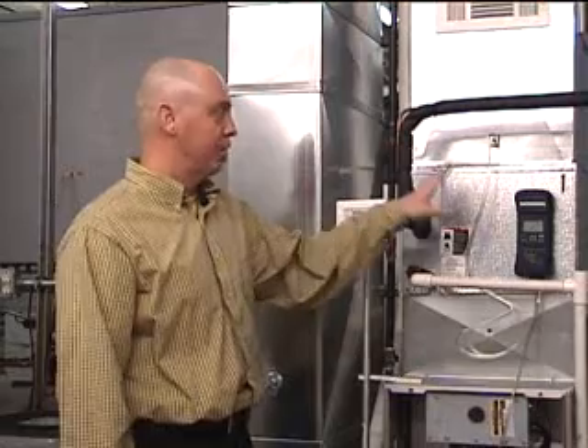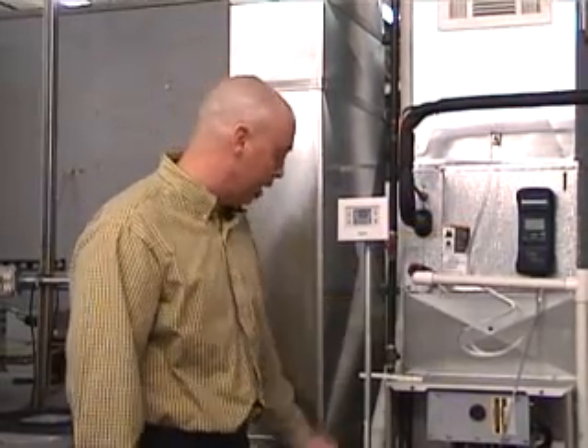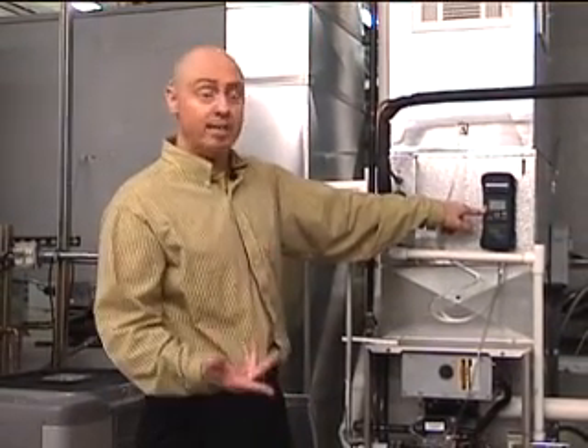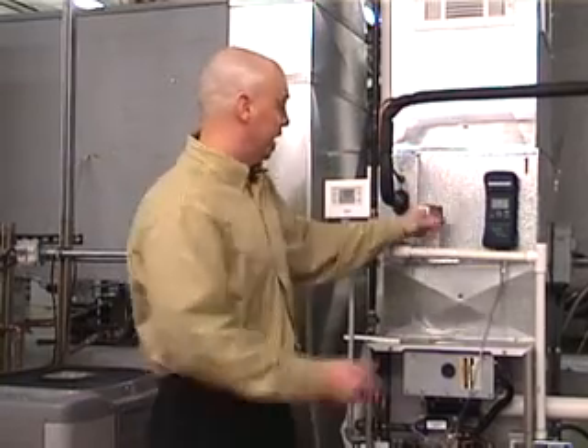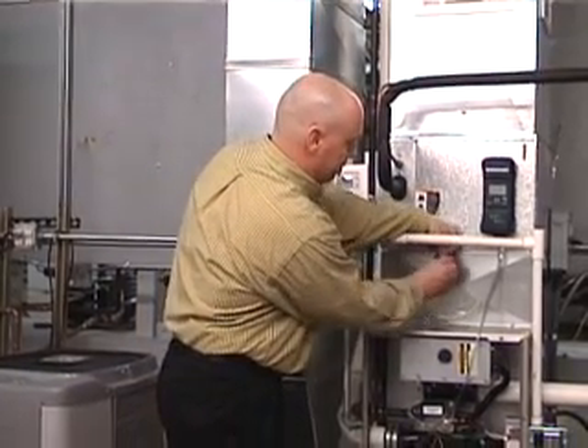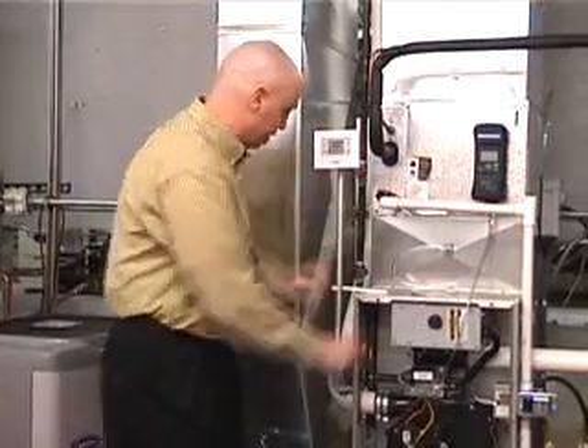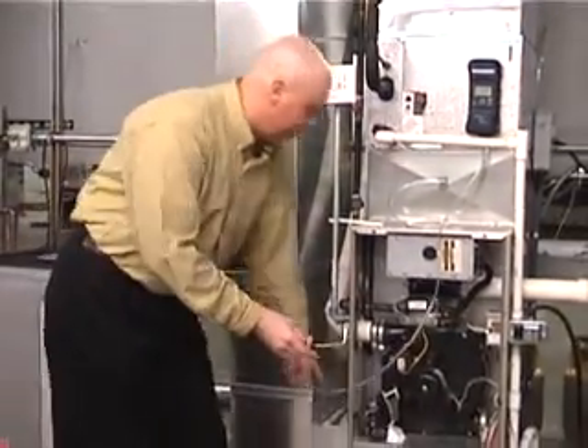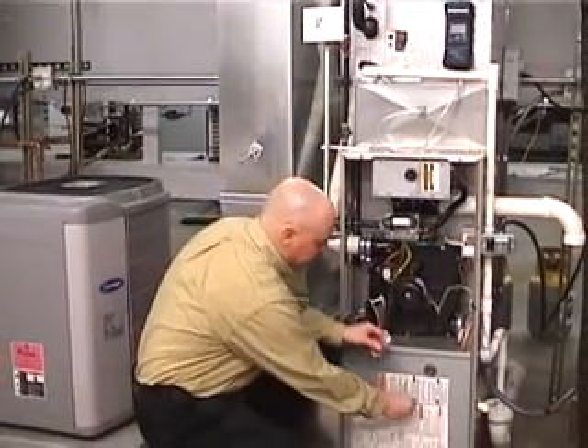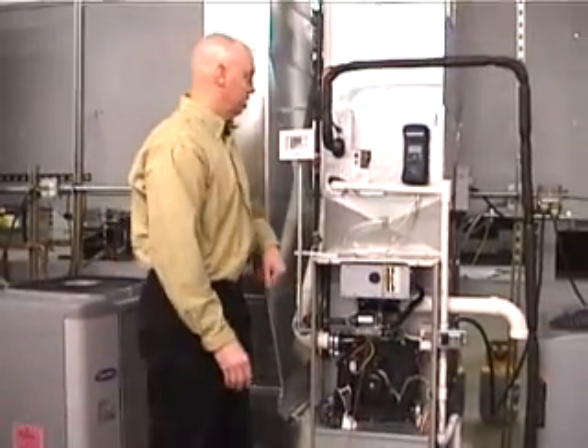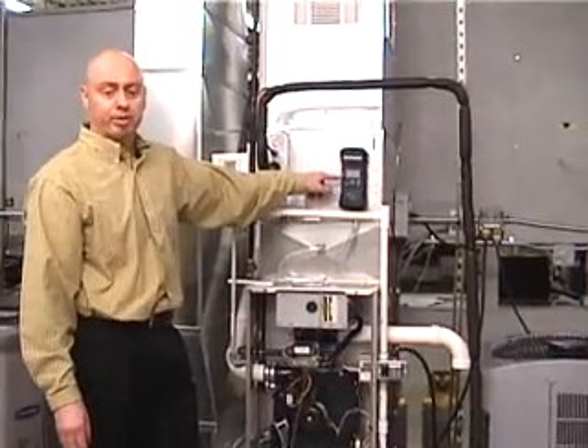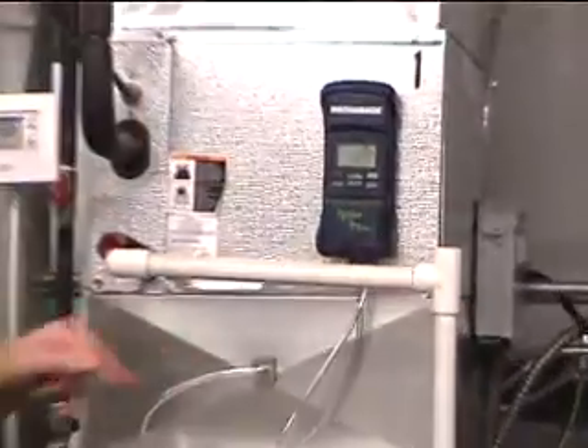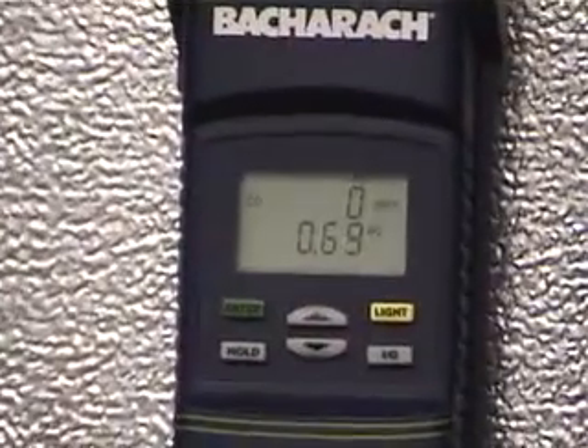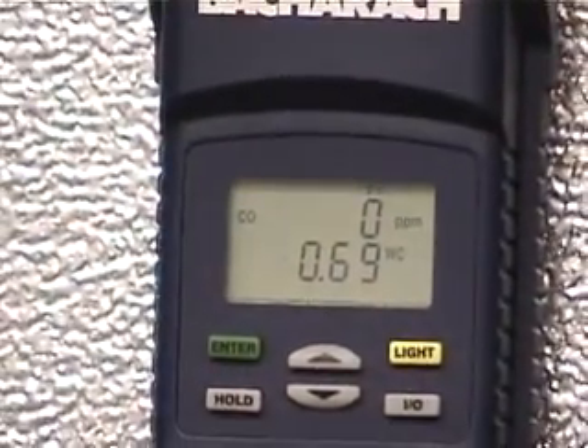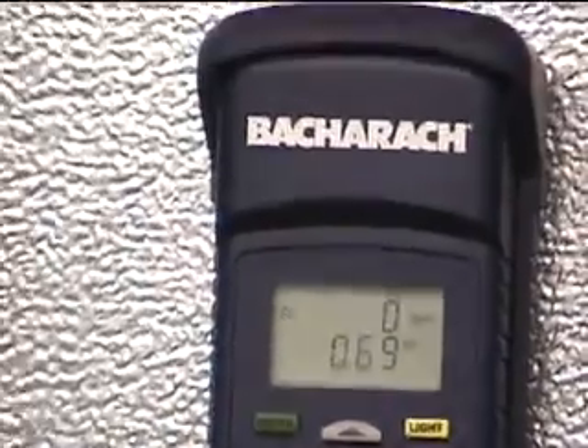But that's not true. That is an actual false positive reading because he did not take into consideration the coil or the filter. What looks like a good number right now, in essence, is a very bad number. It's a very high static pressure. If he was to actually put his probes in the correct location, and again, between the coil and the furnace, and between the filter and the furnace, you will see my actual static pressure is not 0.24, 0.23. My actual ESP, external static pressure for this piece of equipment is 0.69, almost 0.7 inches. So it's way higher than what the allowable level is.